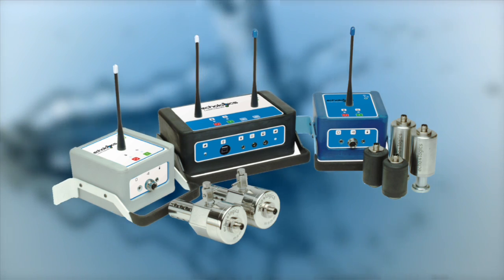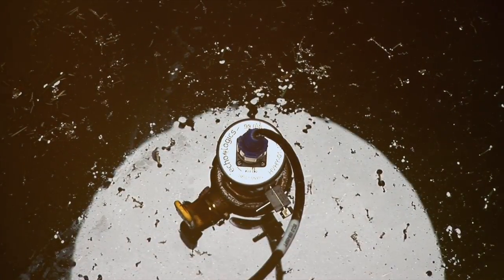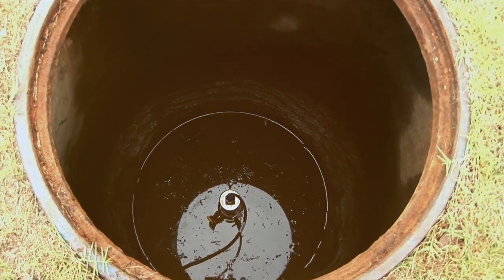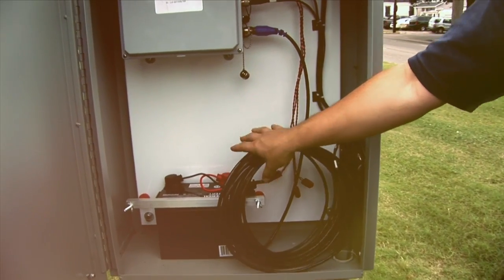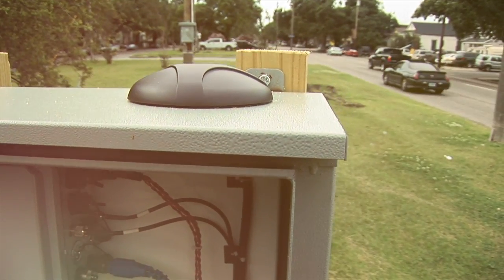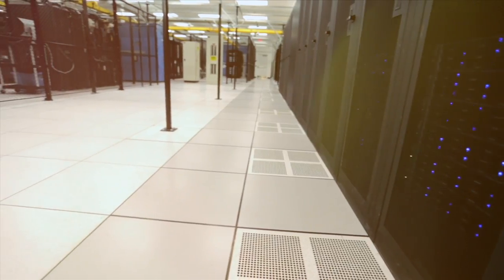Its leak detection capabilities are based on LeakFinder RT's advanced hydrophones and algorithms. A hydrophone is installed in the take-off port of valves in at least two different locations along a transmission main, where they collect synchronized recordings of acoustic signals from the pipeline. Enclosed nodes installed within close proximity to the hydrophones store the recordings before generating reports that are periodically transmitted by cellular technology to Echologics servers.